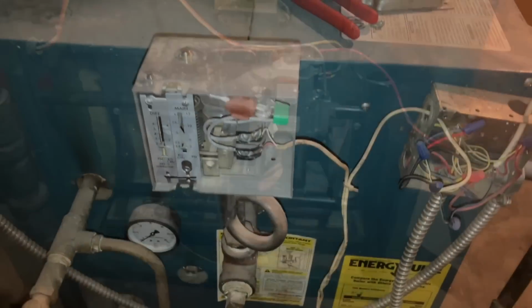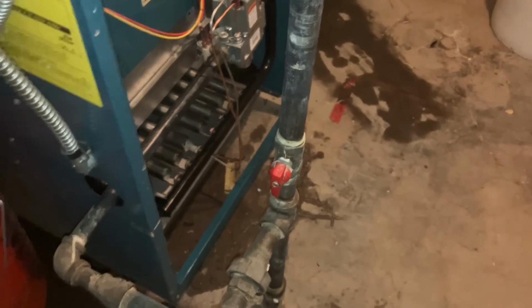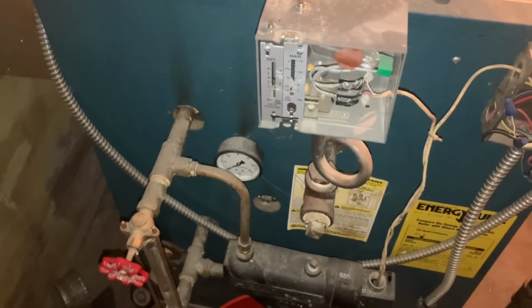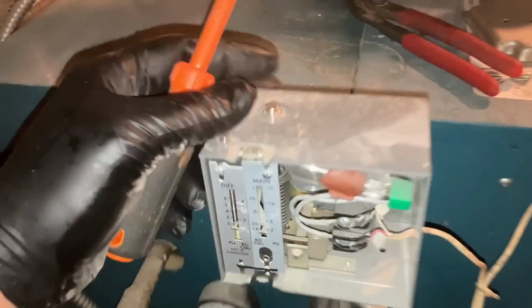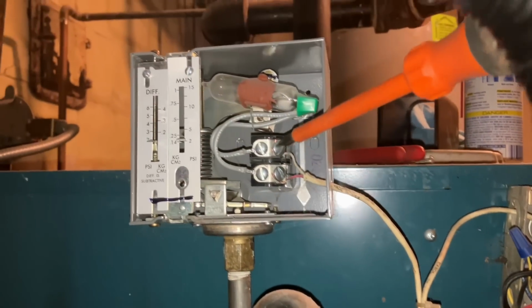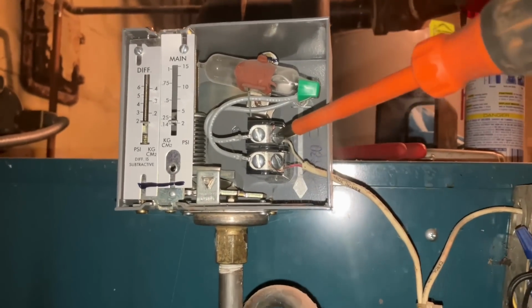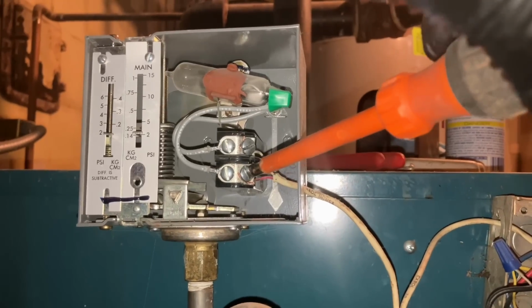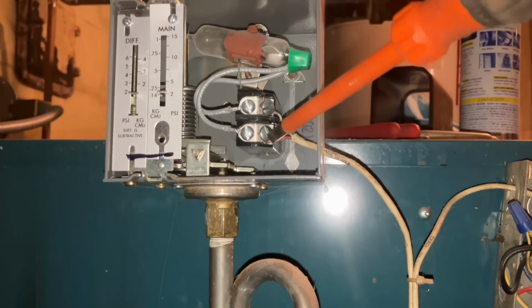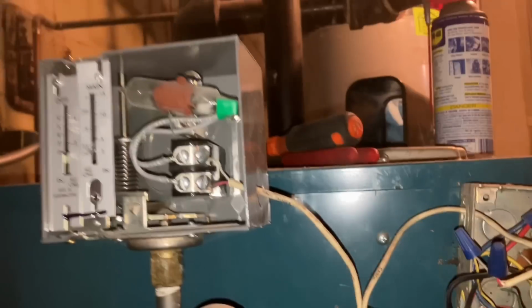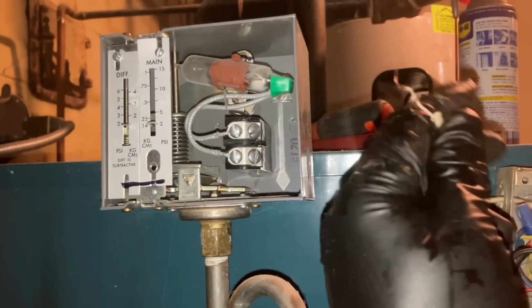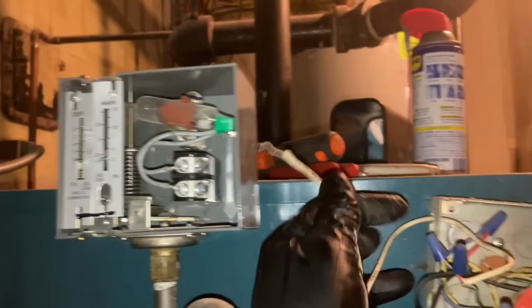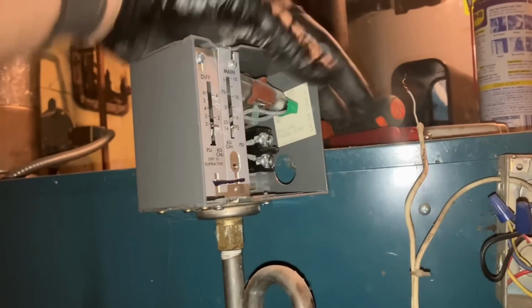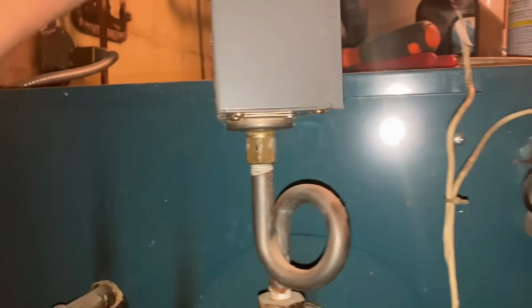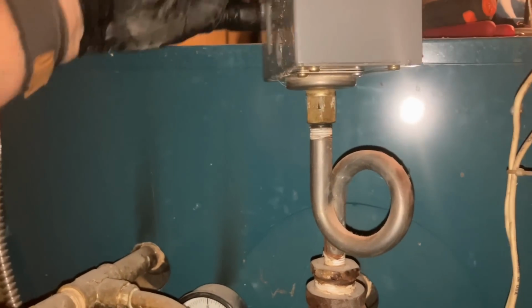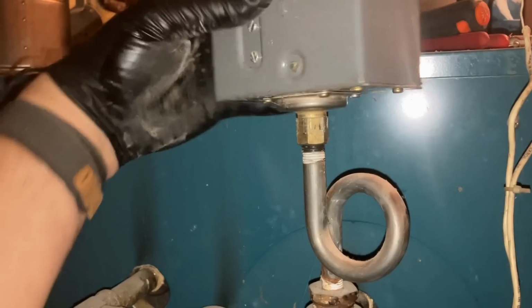Beautiful. All right, now that we're done in the boiler vestibule, we're dealing with the gas. Let's go over here to the left side of the boiler. The cover is missing on this pressuretrol. I'm just going to use a flat screwdriver, removing the two electrical terminals, loosening up the low voltage control wiring going to that. The purpose of this is to take off the pressuretrol from the pigtail. We want to make sure the pigtail is clean. So let's carefully pull this off.